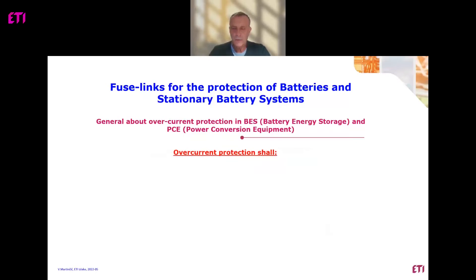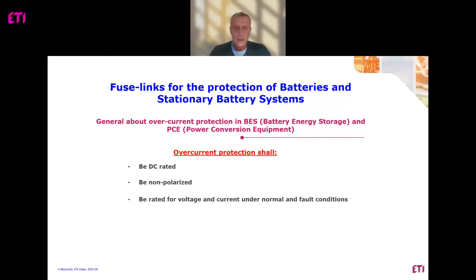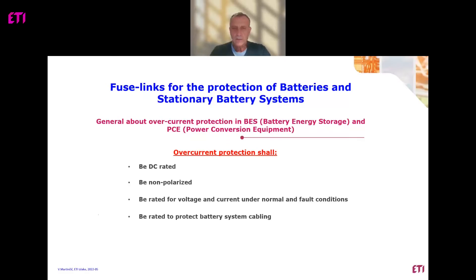What overcurrent protection shall fulfill: one of the most important requirements is that overcurrent protection shall be bipolar. Then it shall be non-polarized. Rated voltage and rated current should be defined under normal and fault conditions. Overcurrent protection should be rated to protect battery system cabling, so connection cables should also be protected. It should meet relevant product standards.